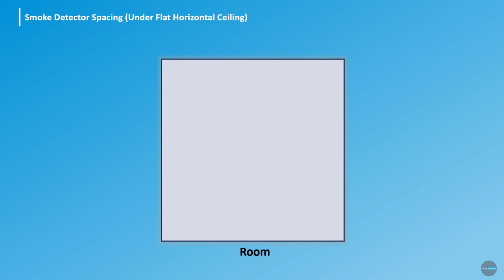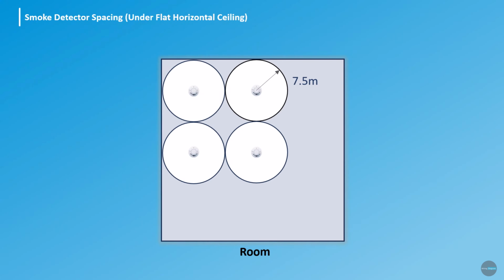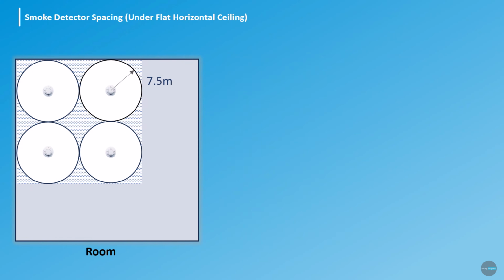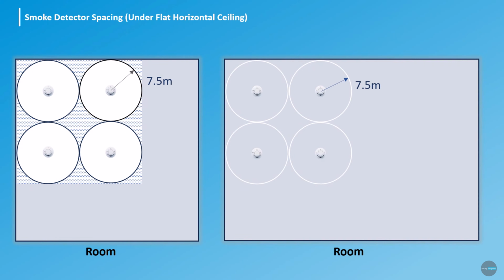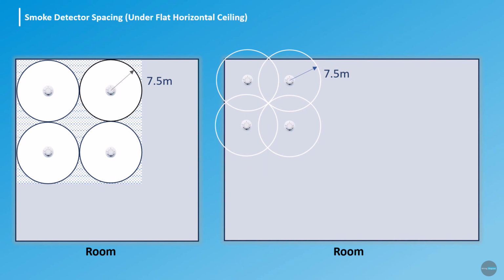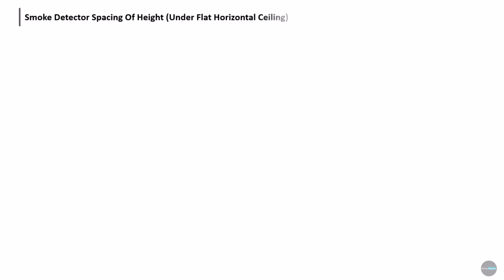Now you may ask, why is that? If we design only based on the 7.5 meter radius, there will be blind areas between detectors, areas that won't be covered properly. But when we space the detectors 10.6 meters apart, their coverage areas overlap and there are no blind zones left. That's why each smoke detector effectively covers an area of 10.6 by 10.6 meters, which equals 112 square meters per detector. Spacing based on ceiling height.